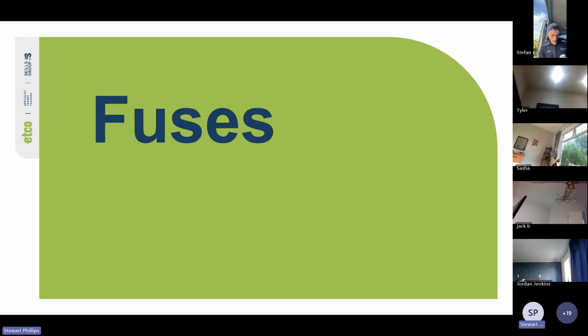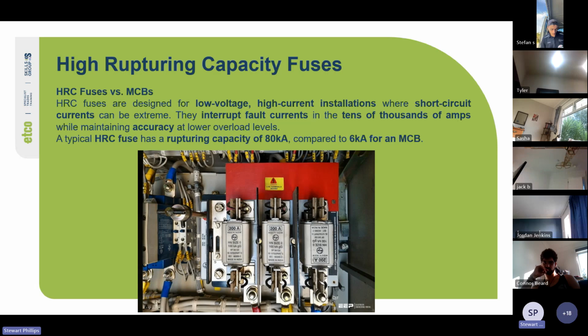Cool. So we'll talk about fuses. So first, high rupturing capacity fuses. So HRC fuses versus MCBs. HRC fuses are designed for low voltage, high current installations where short circuit currents can be extreme. They interrupt fault currents in the tens of thousands of amps while maintaining accuracy at lower overload levels. A typical HRC fuse has a rupturing capacity of 80 kA compared to 6 kA for an MCB.